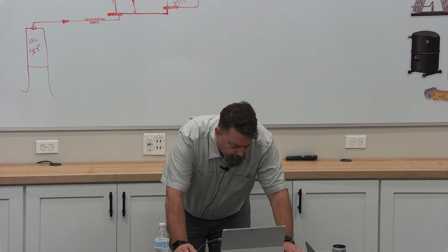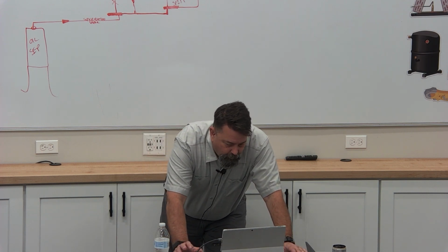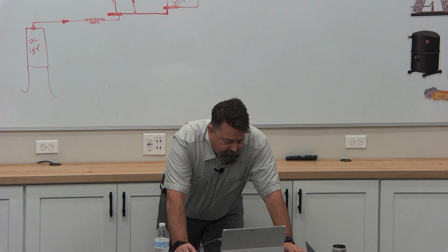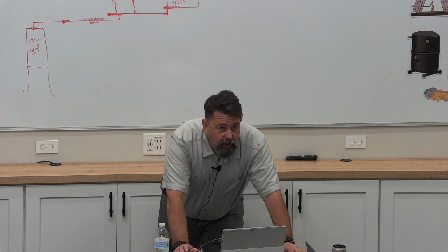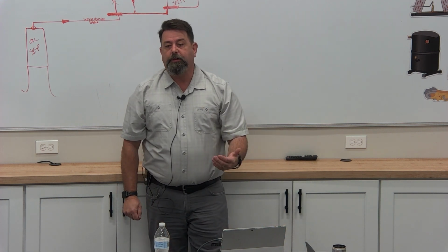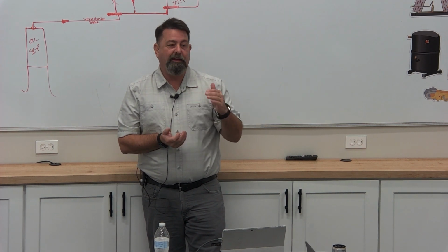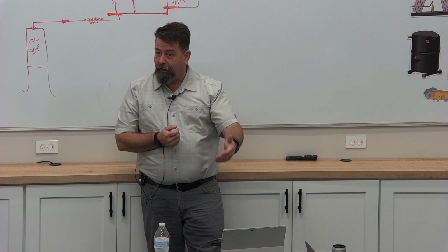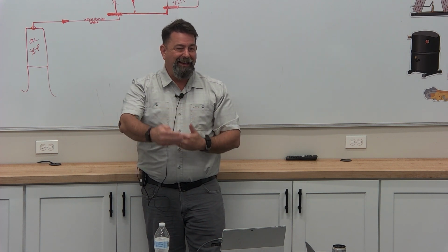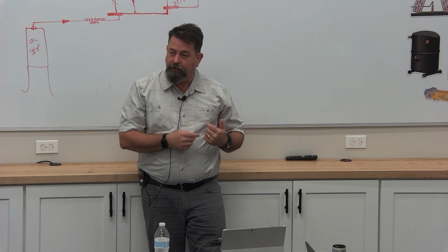All right, so a couple other things. That was the big thing I wanted to talk about, is I must have the proper number of shelves. Every one of my manufacturer's books is going to show me the proper shelves and how many, right? It'll say I can have 4, I can have 5, I can have 6. It'll tell me how many inches they can be for each of those configurations.